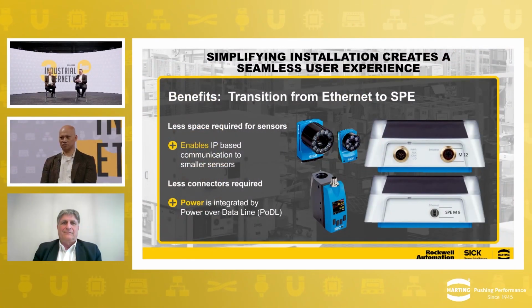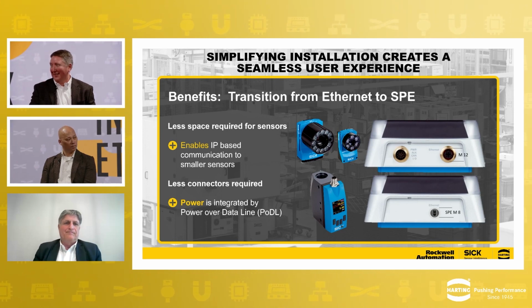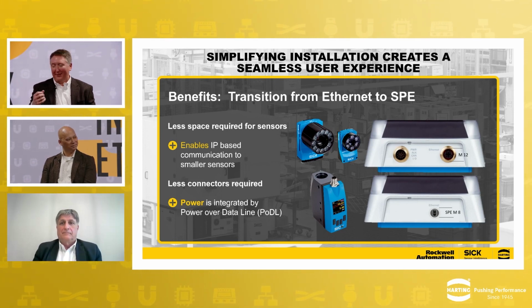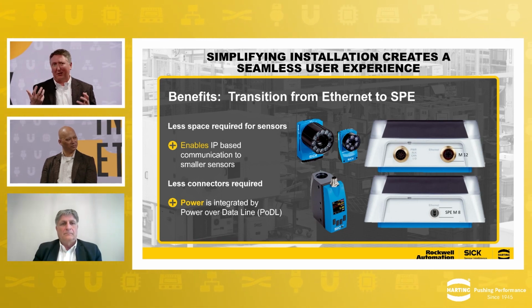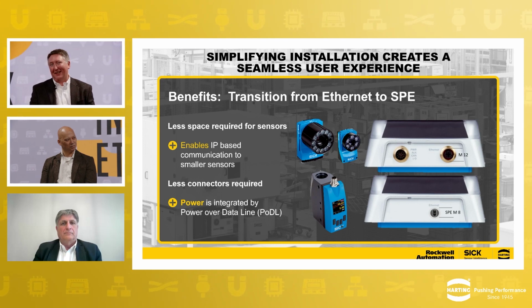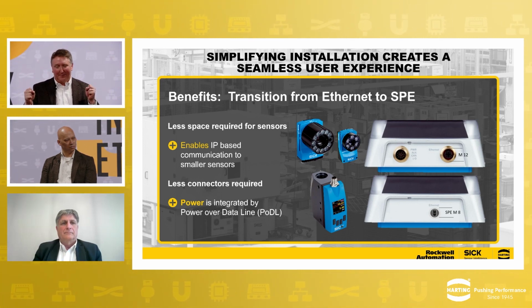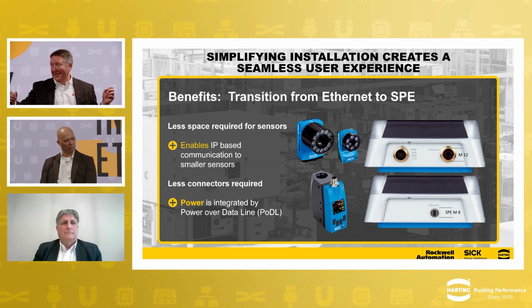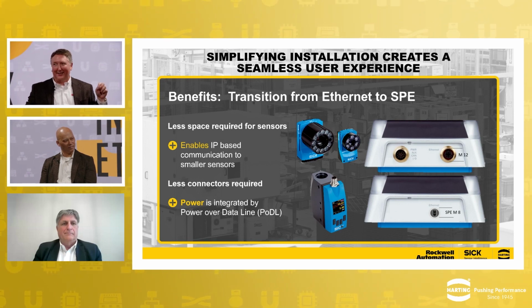This is a really good question. If you talk about power over Ethernet, or PoE as it's called, the same mechanism is also built into single pair Ethernet. It's called power over data line, or PoDL for short, and it works in a very similar way. Yes, it's possible. Even for the 10BASE-T1L, the long single pair Ethernet, it's really meant to replace the old 4 to 20 milliamp signal. Traditionally with those it was 2 wires that could go a long distance, but it's just an analog signal, so you can only get one piece of information out of, say, a flow sensor. By implementing single pair Ethernet, specifically 10BASE-T1L, you reuse the exact same wire, and all you're doing is swapping out the communication, the smart device, and the gateway.